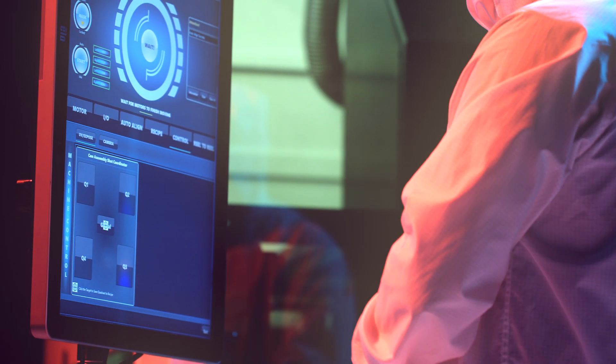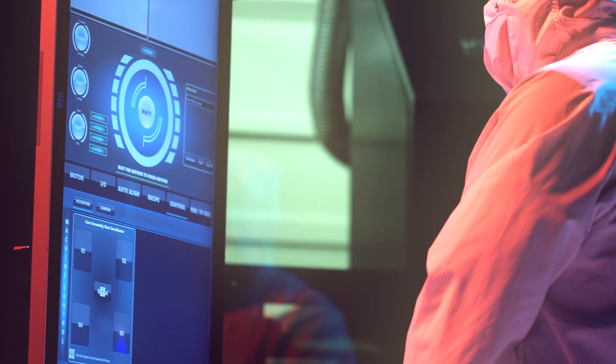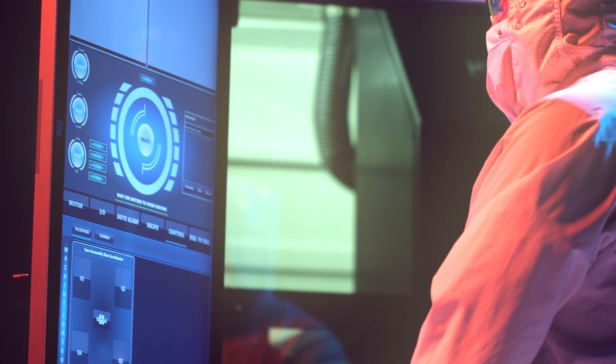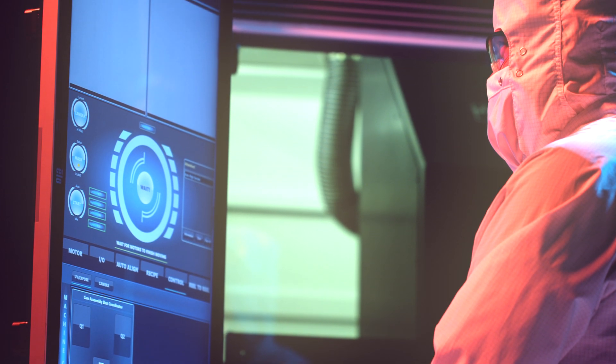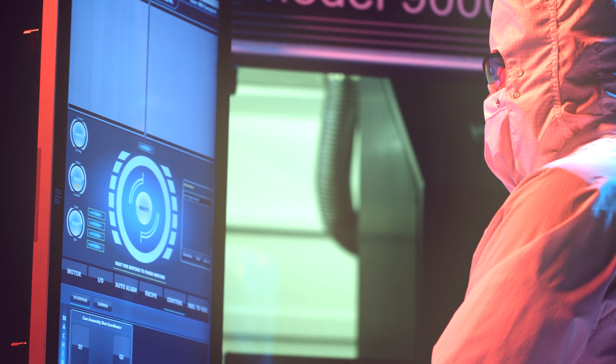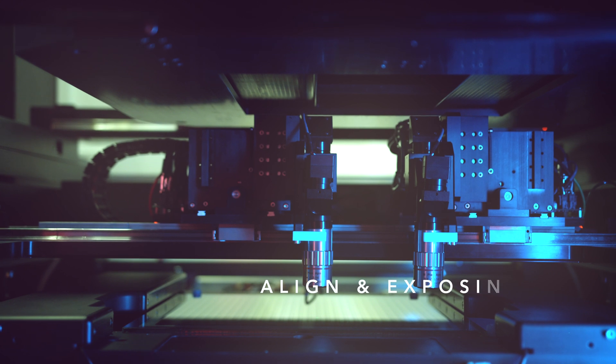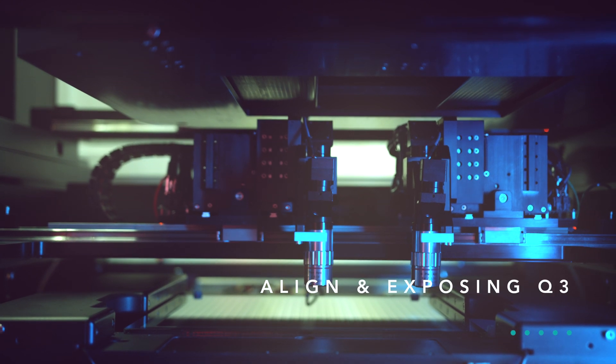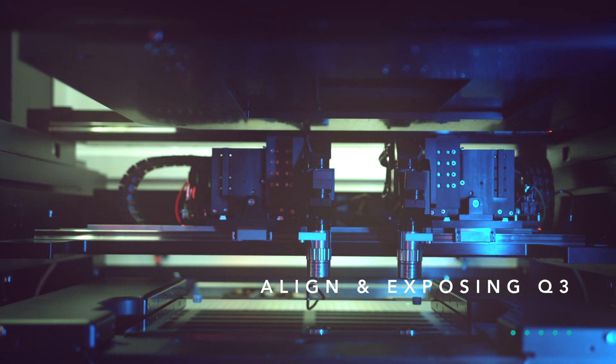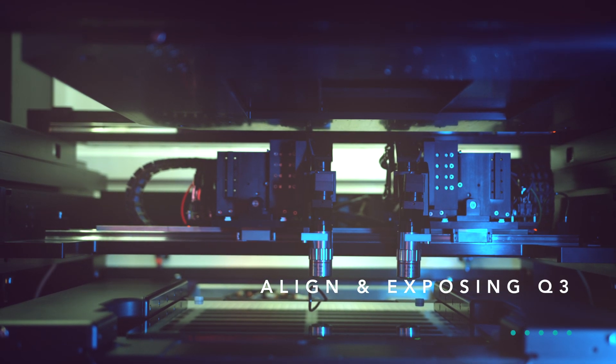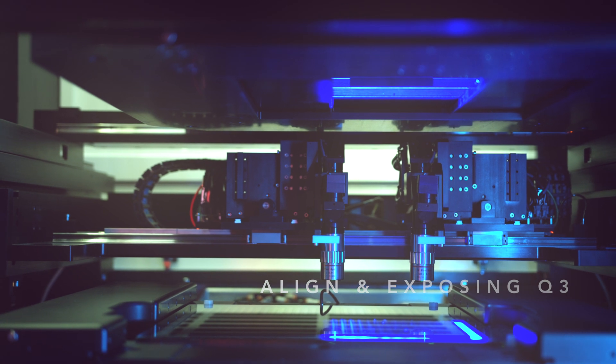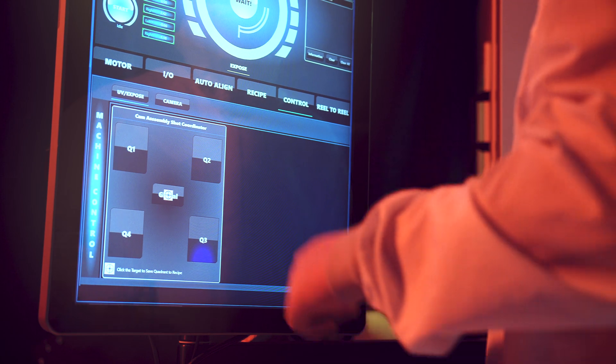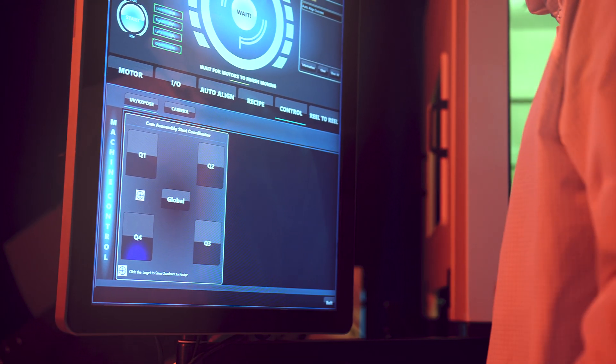With one button click in the recipe, the user can choose between 1X full field alignment or step and repeat exposure. With 1X full field alignment, substrates up to 320 mm square are aligned globally then exposed in one shot. Field shutters are used to define the exposure area.